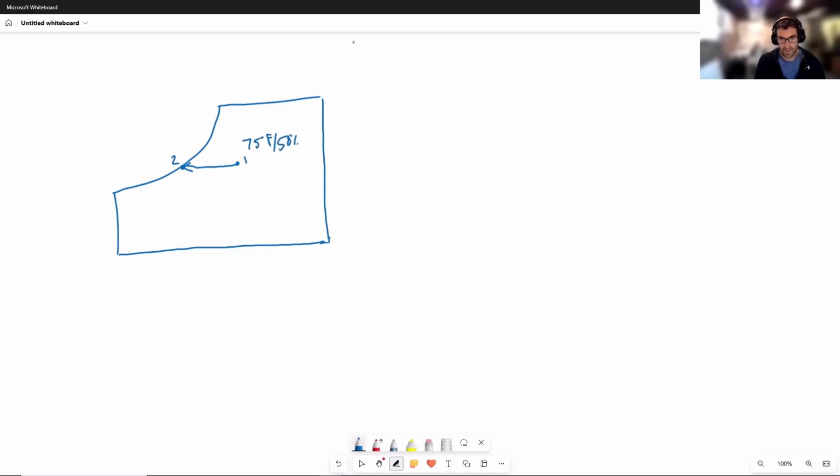For that fully defined state, we can look up the dew point. We can use a psychrometric calculator, or we can use the psychrometric chart, find that point, and move horizontally to the left until we hit the curve. Whatever temperature we hit the curve at is the dew point temperature. You can read that off the horizontal axis, or directly off this curve.